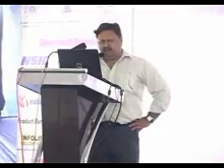There are two kinds of time of flight analyzer. One is a simple TOF. TOF stands for time of flight. So the simple TOF, which is the LC-MS instrument, does not have the fragmentation capabilities. But if I add a quadrupole and a collision cell into it, I get fragmentation capabilities. So what is the importance of having TOF and accurate mass?